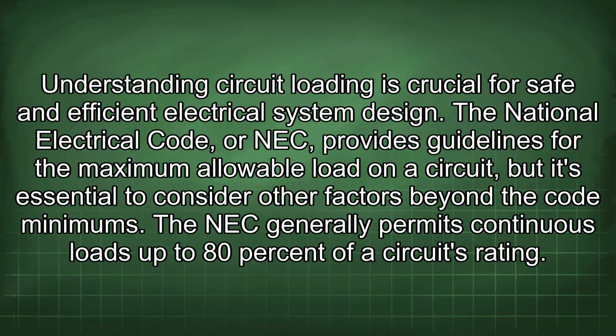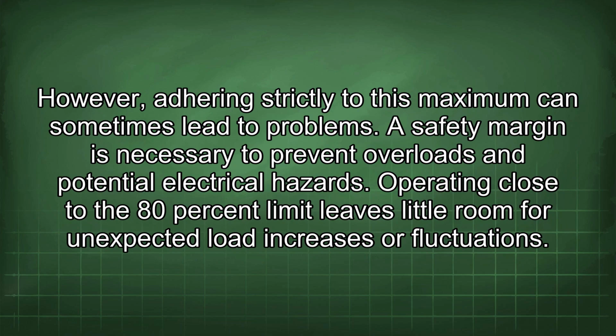Understanding circuit loading is crucial for safe and efficient electrical system design. The National Electrical Code, or NEC, provides guidelines for the maximum allowable load on a circuit, but it's essential to consider other factors beyond the code minimums. The NEC generally permits continuous loads up to 80% of a circuit's rating. However, adhering strictly to this maximum can sometimes lead to problems.